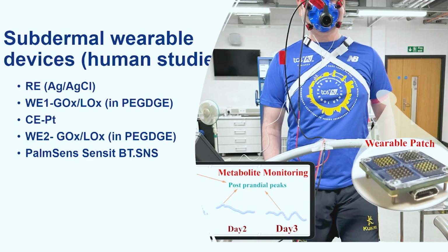How we were using it in terms of looking at the performance, somebody mentioned interference with sweat. Who was this person? There was a gentleman who raised, yeah, so interference with sweat. Here's your answer. You can see the devices here. As you can see, there's also a thin film covering the base of the devices as well, so that you don't get any sweating when you push them into the skin. And these needles are only under your skin, so they will only measure what's under your skin and not what's over your skin as well.